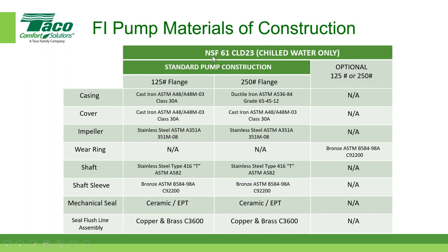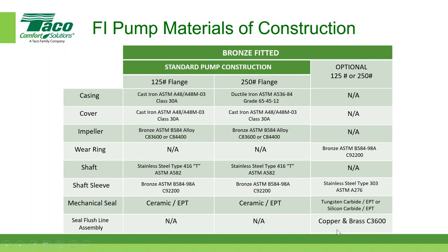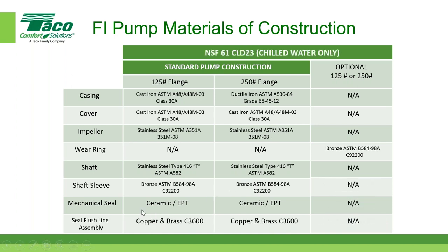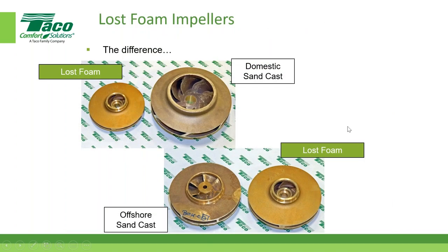We do offer for the CI and FI pumps an NSF rated one for chilled water only, and its rating is for CLD23. You can see some of the materials of construction here are pretty much the same, except you'll notice the impeller is stainless steel instead of bronze. Everything else is pretty straightforward. It does have to have the seal flush line assembly kit. You can see on the other ones that was an option. You could add it for the FI pumps, but on the NSF rated one, you do need that kit sent and installed.